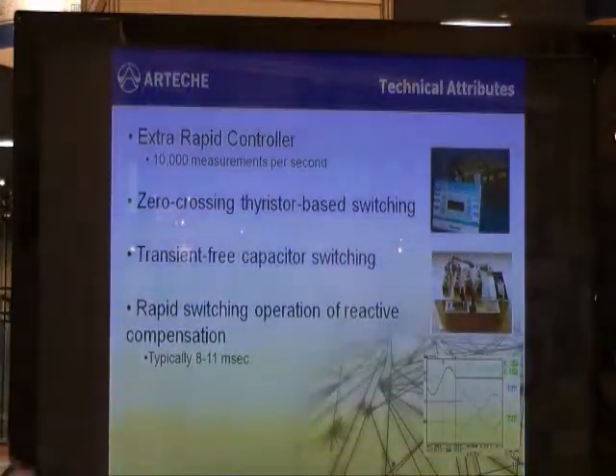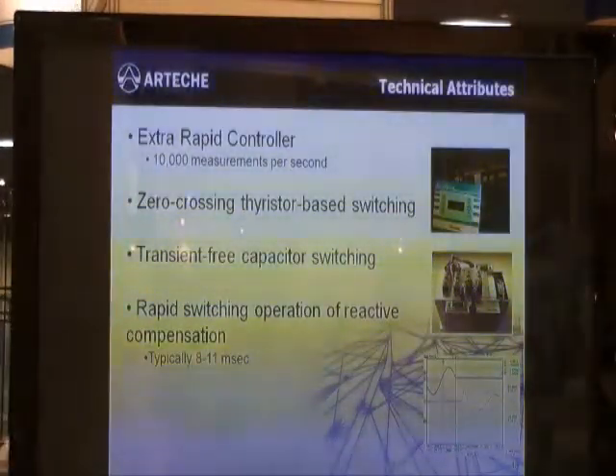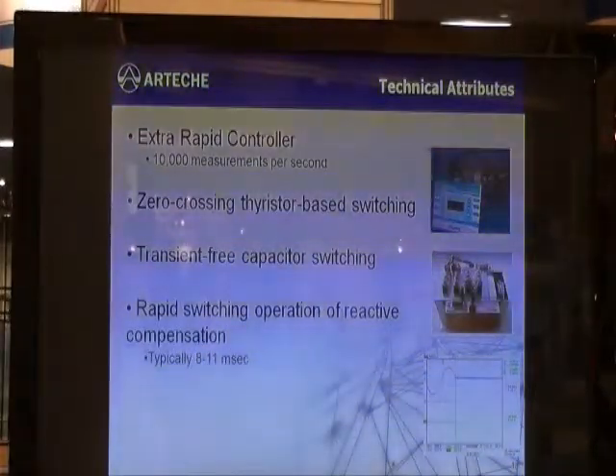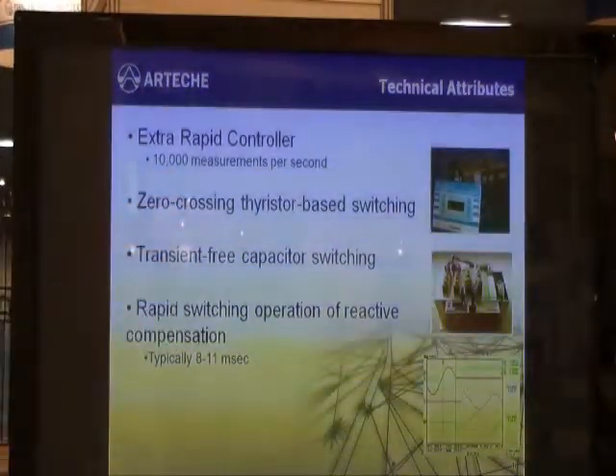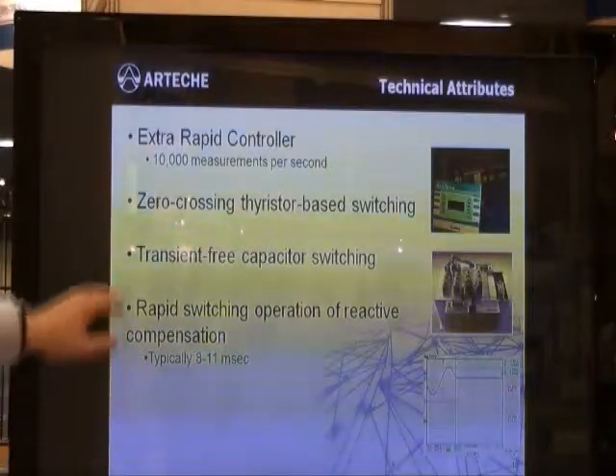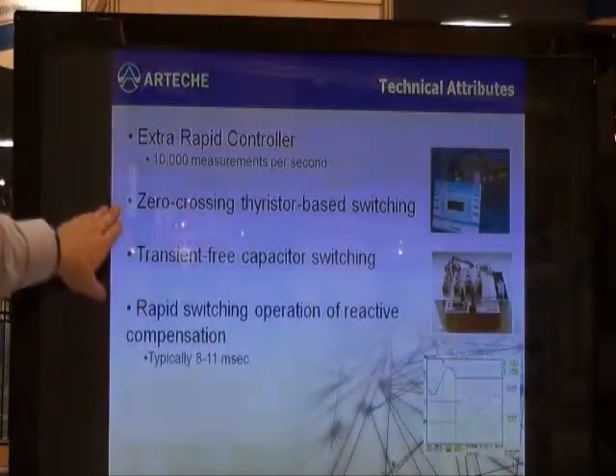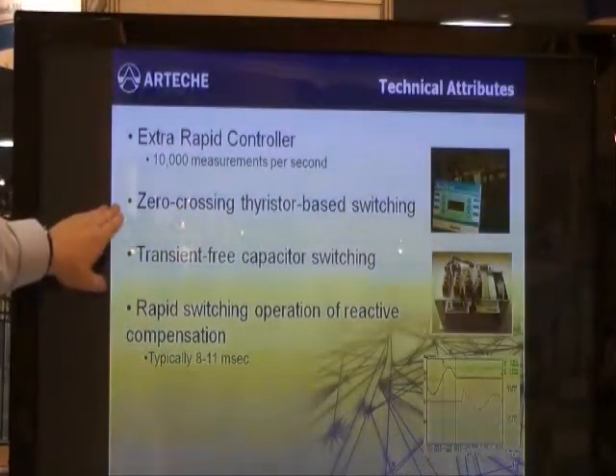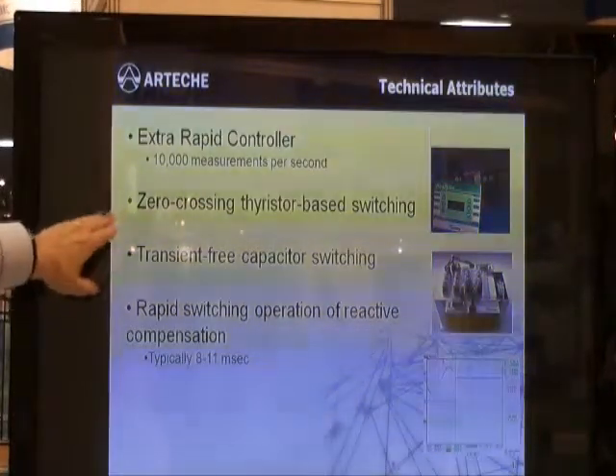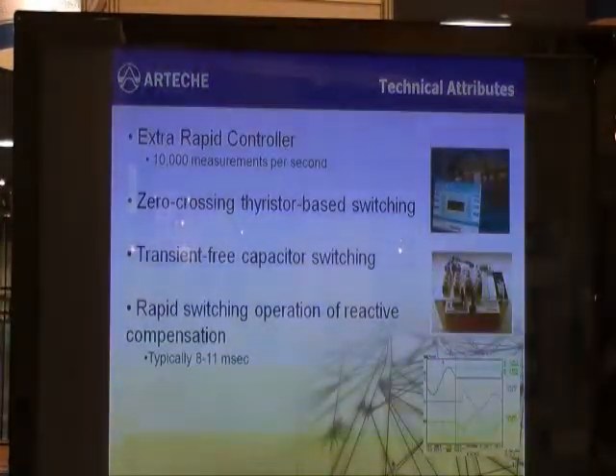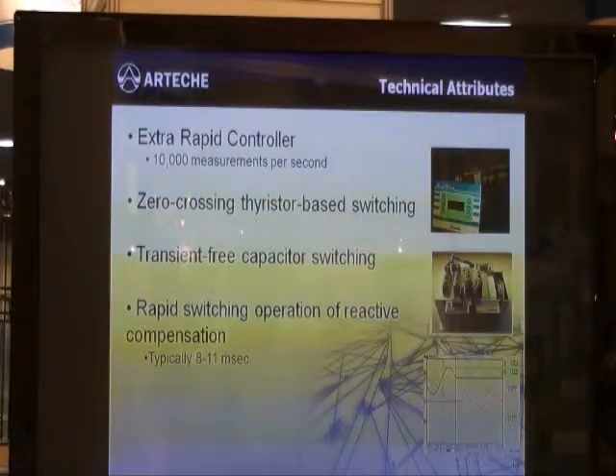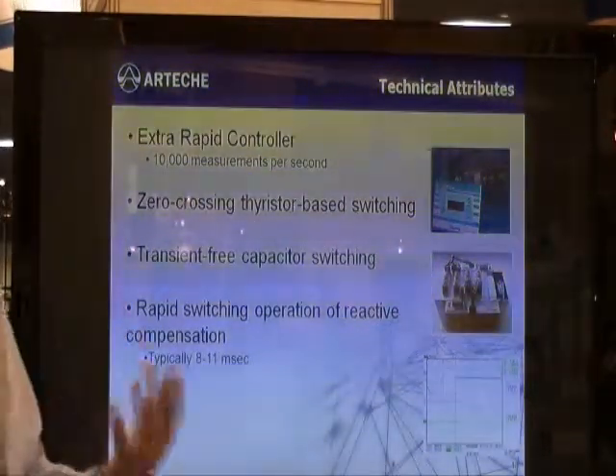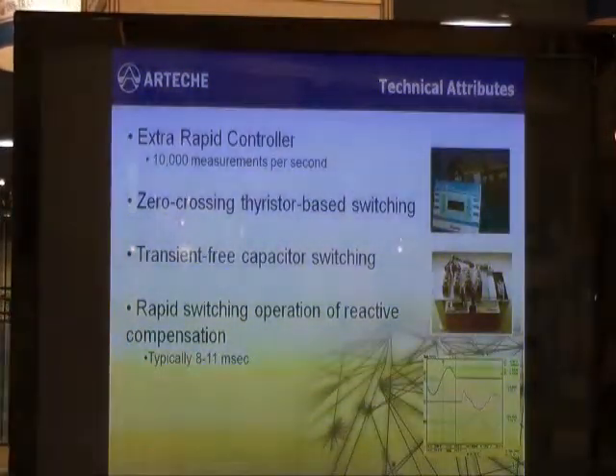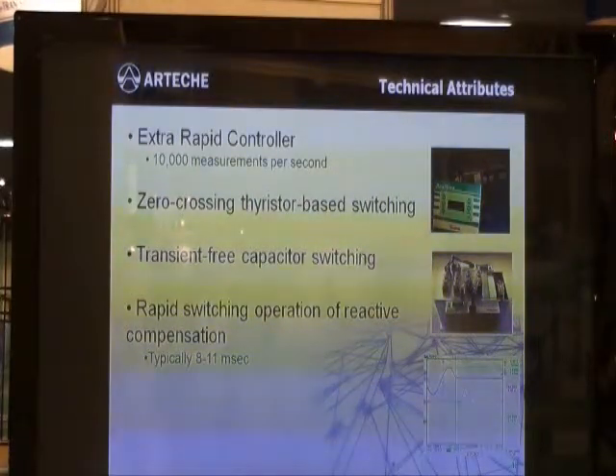The attributes of this product were first that it had a very high speed controller or extra rapid controller which can take 10,000 measurements per second. It utilized our zero cross thyristor switching system, offered transient free capacitor switching, and rapid switching of the complete capacitor system in typically 8 to about 11 milliseconds.